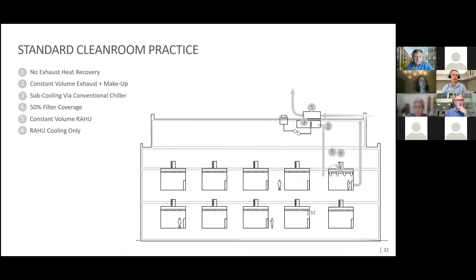That included exhaust heat recovery, variable volume exhaust, variable volume air change rate in the clean room, particle counters and occupancy sensors, as well as 100% filter coverage on the ceilings of the clean room space, so that all that air that has to flow through can flow as smoothly and easily as possible and use the least amount of fan energy.